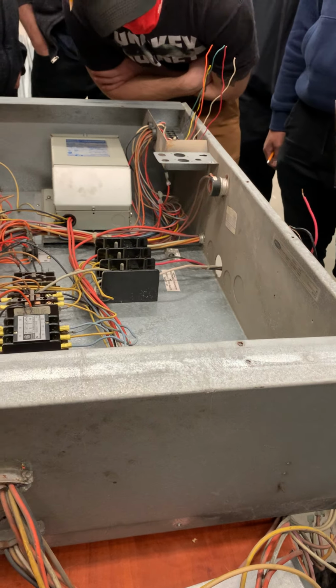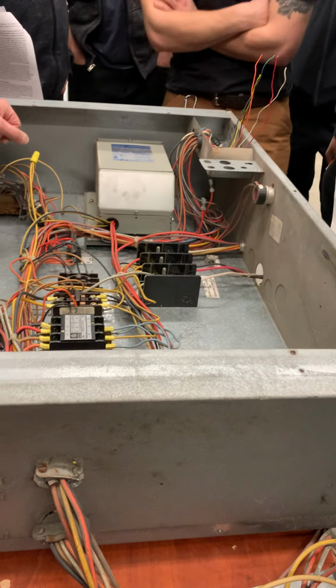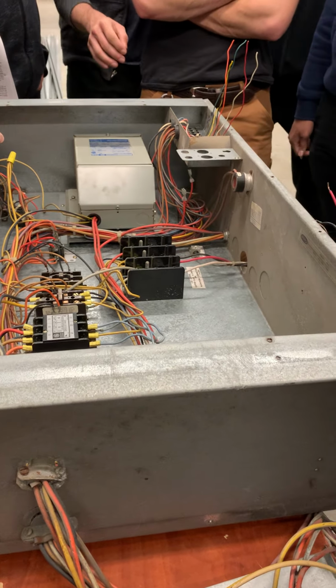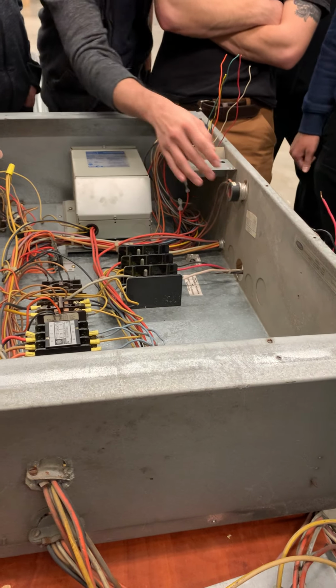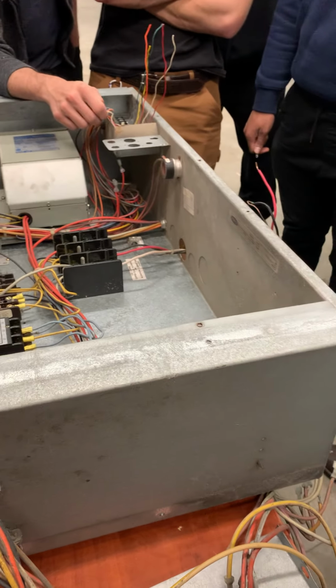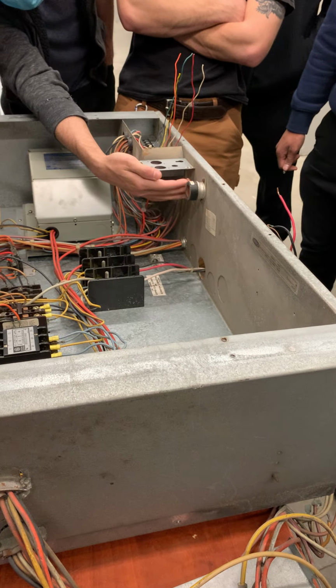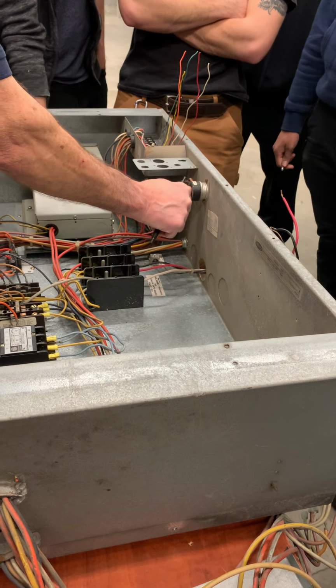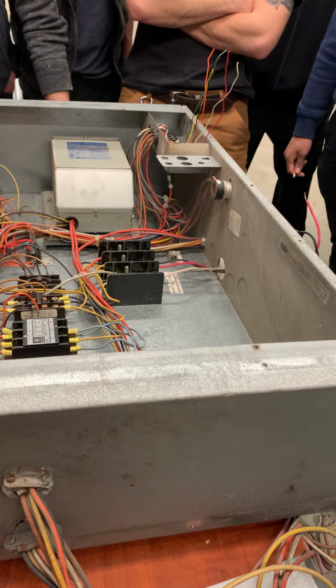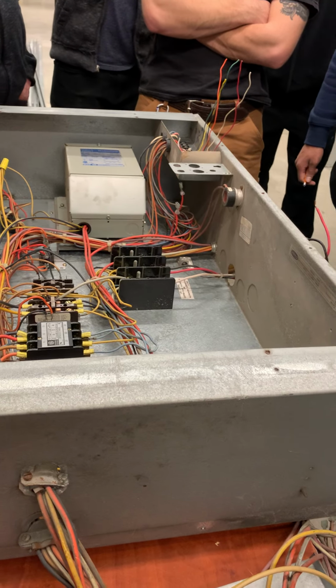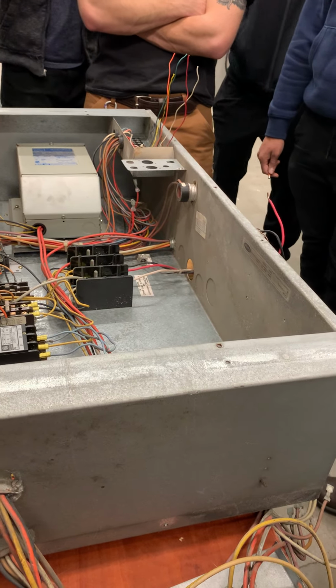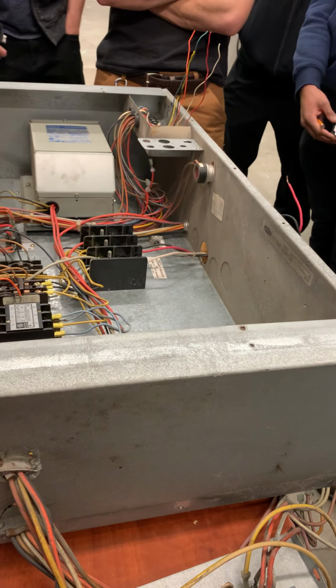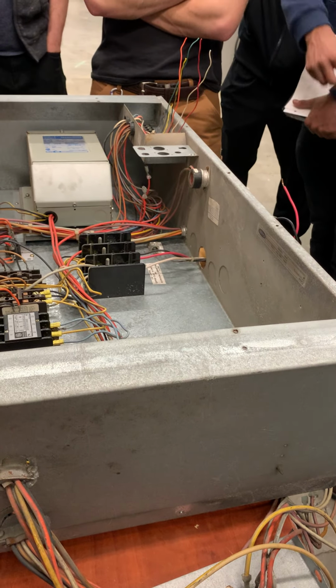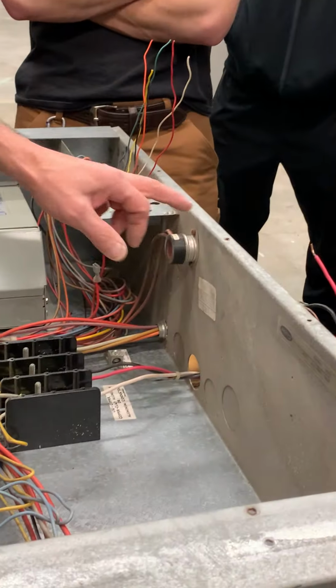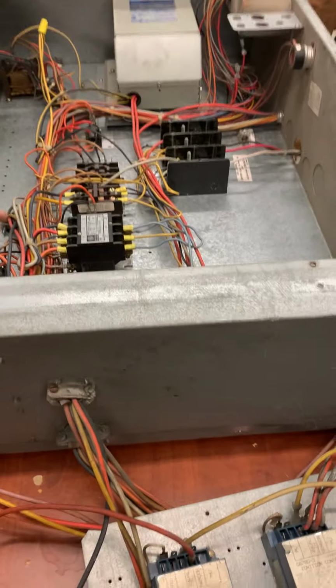It's got 2 wires going to it, and a fuse. It kind of looks like it's got a red section back here, like it's a push button or something. But all it is, it's a low ambient thermostat. So if it's cold outside, we're not going to run the compressors. We're going to safeguard the compressors. So low temperatures like today, we won't allow the compressors to run, and that's my low ambient thermostat.